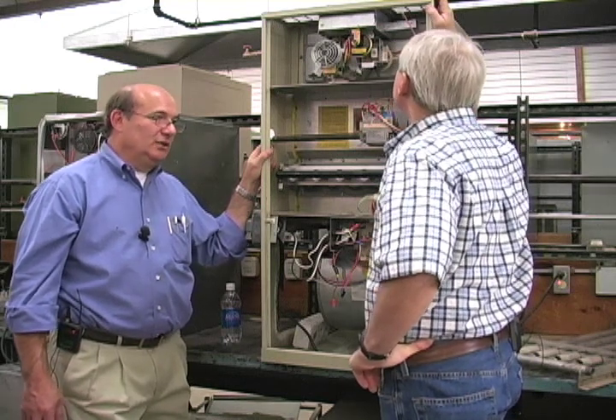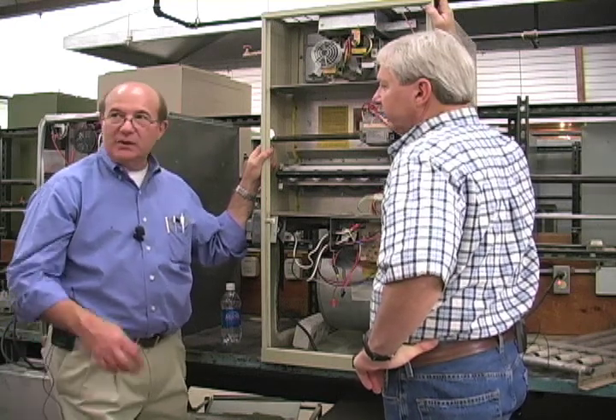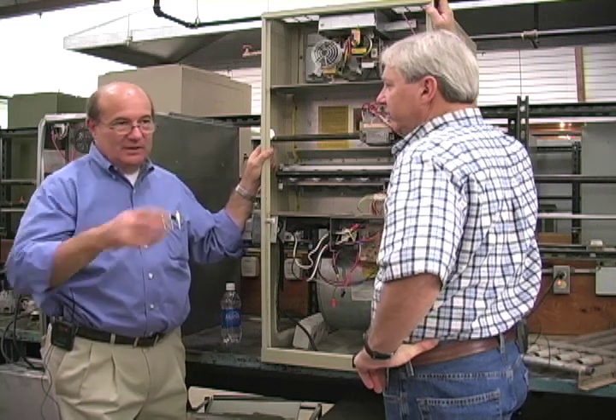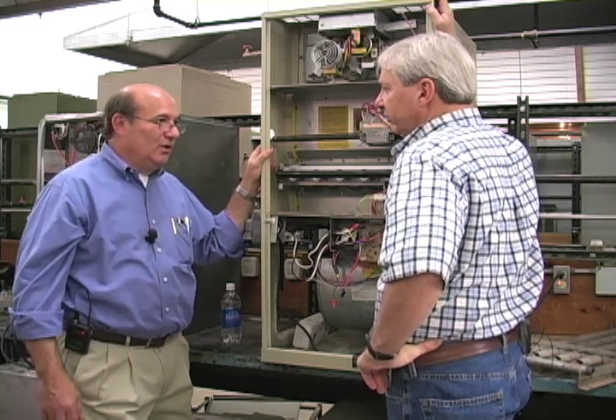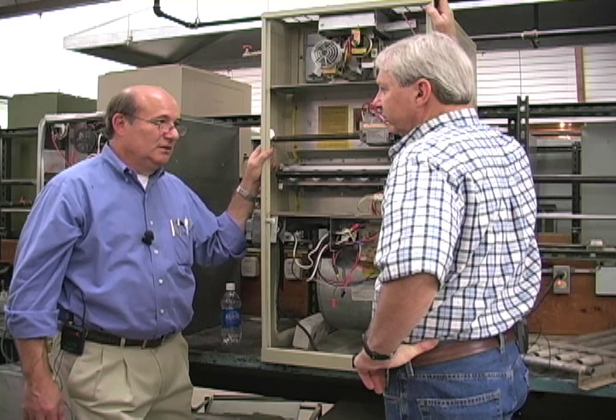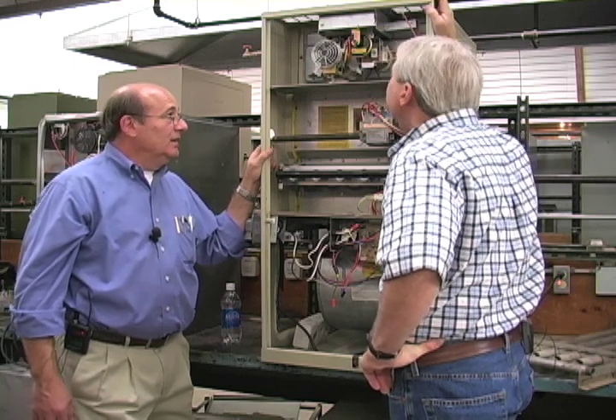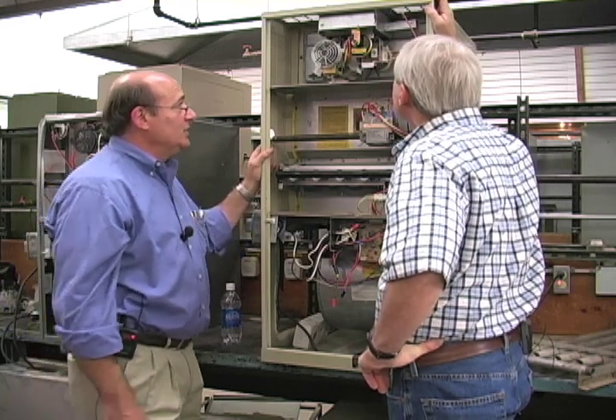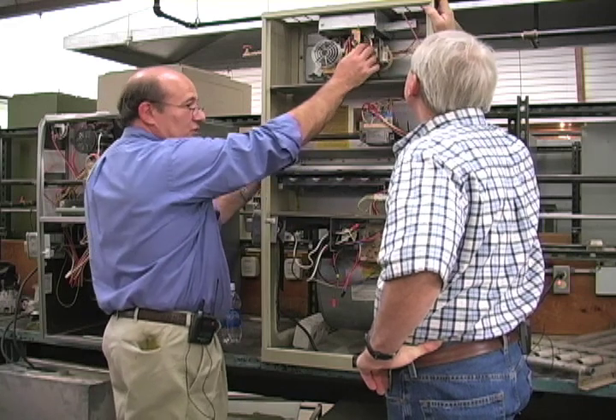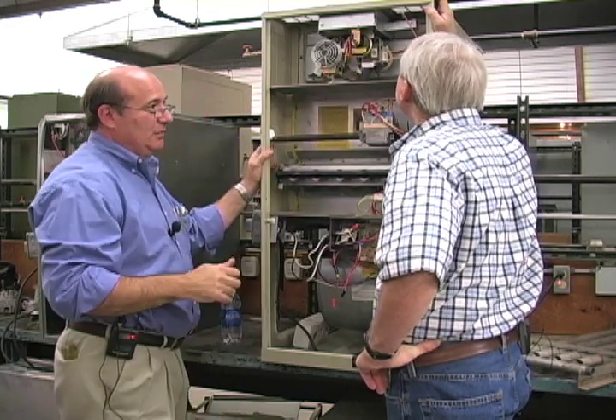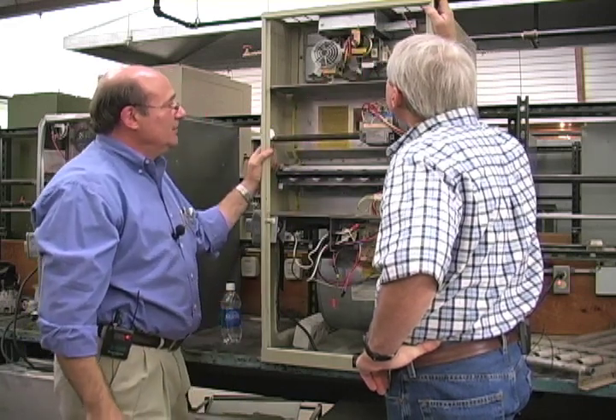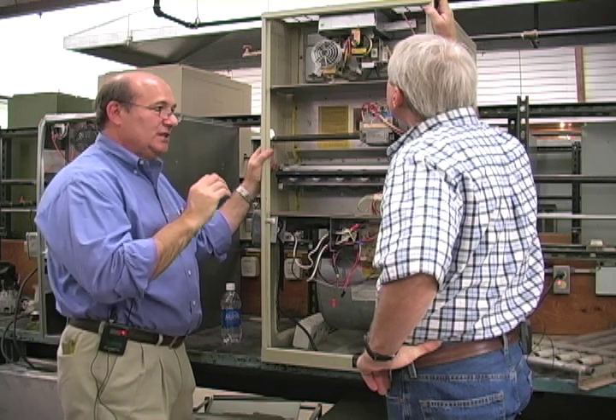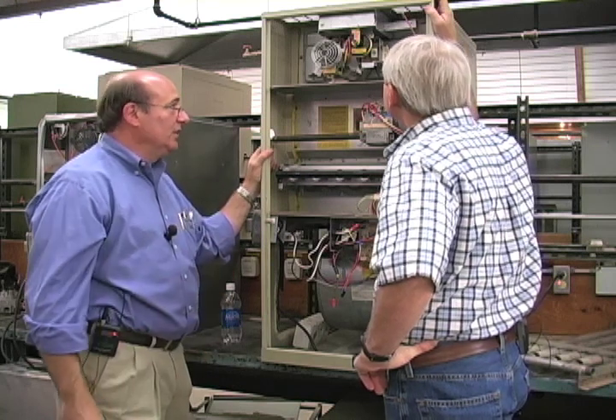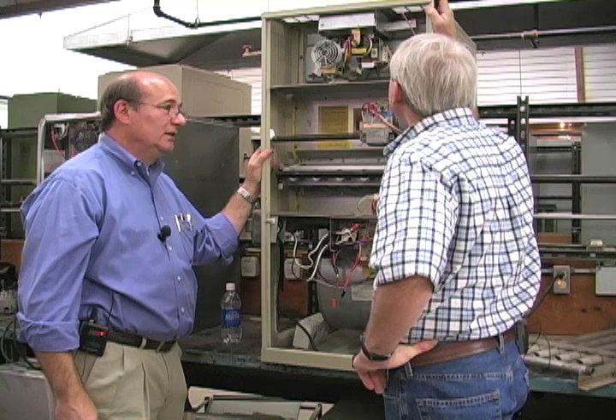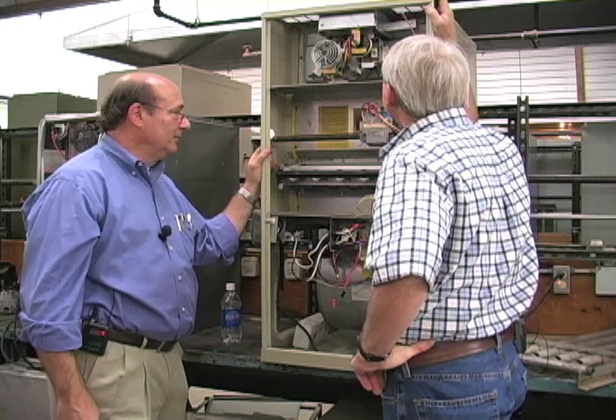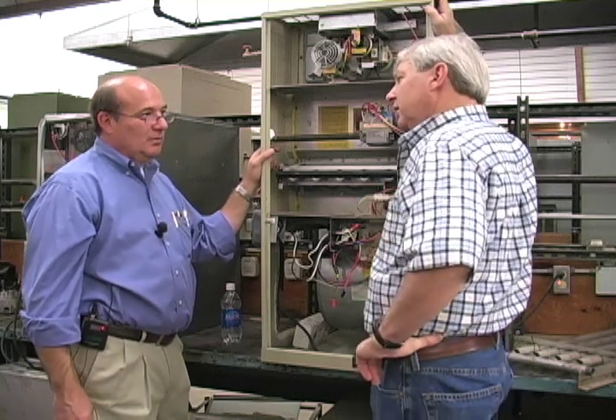When we deal with locations at altitude, like Denver, or certainly if we're going up into the mountains somewhere, we might see very low pressures because the air is so much lighter. A lot of the furnace manufacturers actually have a replacement pressure switch that they'll ship you for a high altitude location because they have to be a lot more sensitive to the lower pressures that we're experiencing at our altitudes here in Denver and up in the hills up here. So that's one potential failure.